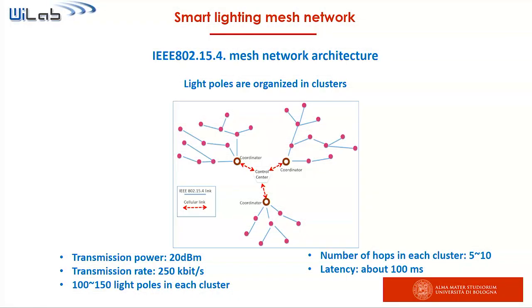This is the network architecture. It is based on the IEEE 802.15.4 communication standard. Light poles are organized in clusters — this example shows three clusters. Each cluster has a coordinator which is able to communicate with the control center, and the information propagates from the control center to the coordinator and then hop by hop to all poles of the cluster.